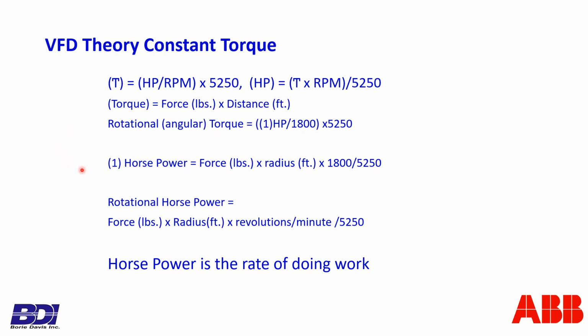Now in the other equation, if we have horsepower as 1 horsepower, and we have unknown pound-feet and radius, well, the pound-feet times 1800 divided by 5250 is going to solve for horsepower. So if it's 1 horsepower, again, if we do the math, to clear this, we'll need to multiply both sides by 5250 divided by 1800. And that'll come up with about 3, which is, again, where the 3 foot-pounds come from. Okay. So the power, the horsepower, is the rate of doing work, and you can solve for it either way if you have the 2 values you need, the radius or the force or the horsepower, and of course the base speed RPM of the motor.